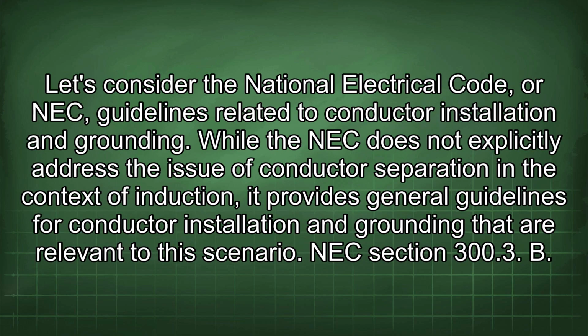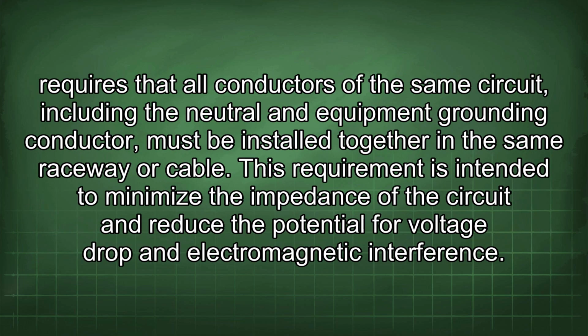Let's consider the National Electrical Code, or NEC, guidelines related to conductor installation and grounding. While the NEC does not explicitly address the issue of conductor separation in the context of induction, it provides general guidelines for conductor installation and grounding that are relevant to this scenario. NEC Section 300.3(B) requires that all conductors of the same circuit, including the neutral and equipment grounding conductor, must be installed together in the same raceway or cable.